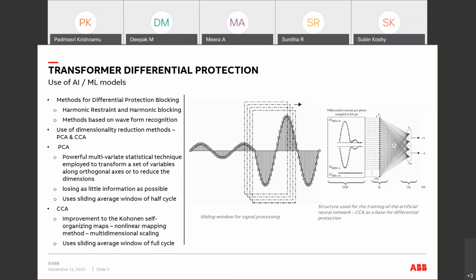The PCA and the CCA algorithms consider the current transformer saturation phenomena and deviations in the power system parameters. Both algorithms were proven by means of time domain simulation of distinct scenarios such as variations in the transformer load, source impedance, turn ratio, and BH curve of the current transformers, and in all of these cases, they could distinguish between the internal short circuit current, inrush, and overexcitation conditions. So this is one literature which indicates that this is a pretty successful machine learning method to handle the transformer differential.